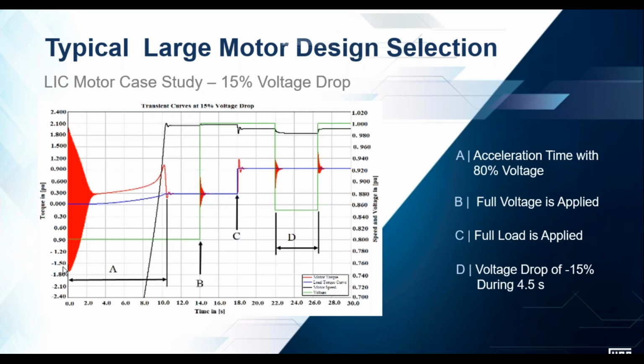So just to go through this quickly, the green curve is the voltage, the blue curve is the load, the red curve is the motor torque. So you can see the motor accelerates the load, which is the blue curve, to a lightly loaded condition, 30% of rated, and then the voltage returns from 80% to 100% of rated, at which time the load is increased. After running for some time, another large motor starts on the platform, and we have a 15% voltage drop, during which the machine suffers a slight dip in speed, which is in black, but continues to operate without stalling.